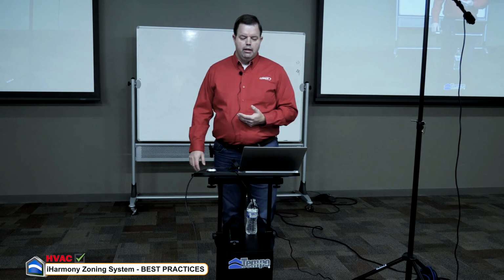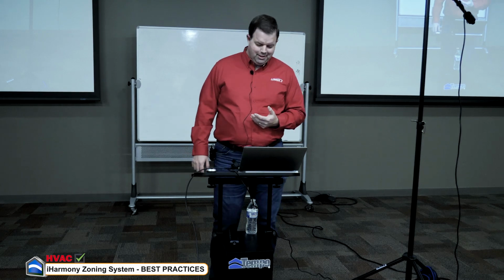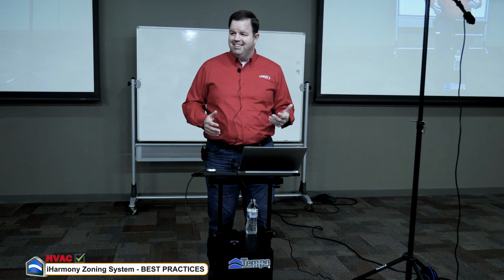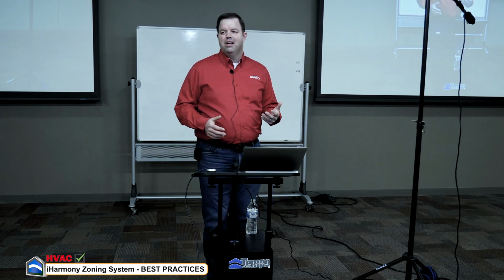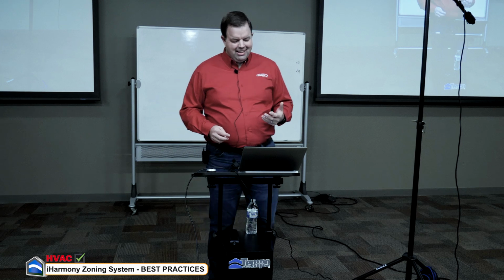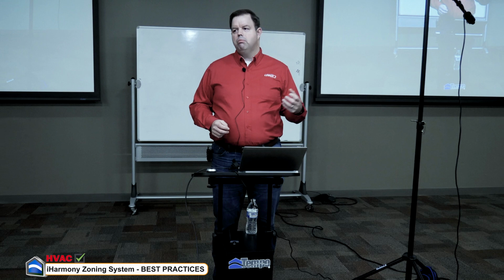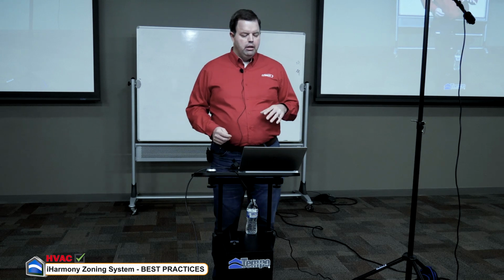Is it required to wire up the leftover wires? When you run into the thermostat and you say that you run an 8-wire and it only takes 4, is it required to wire up the leftover 4? Yes. 8-wire haunts my dreams at night. Or a 6-wire, and you go to the S30 and only use 4. Do you wire nut those? Yeah, you want to wire nut those and take them to common.